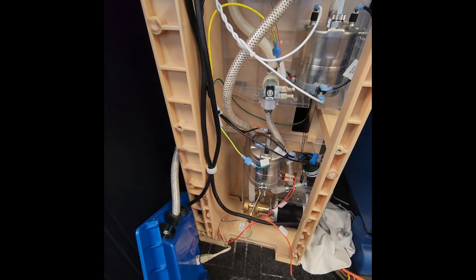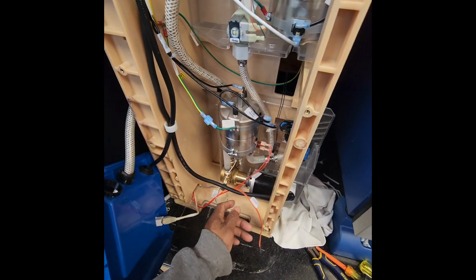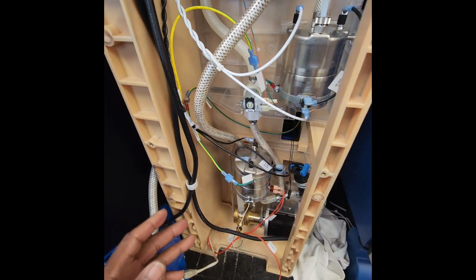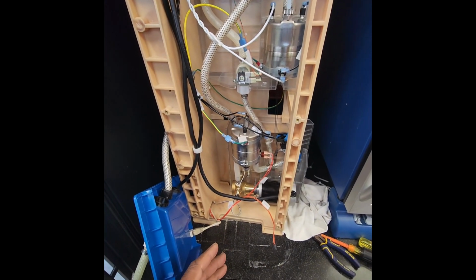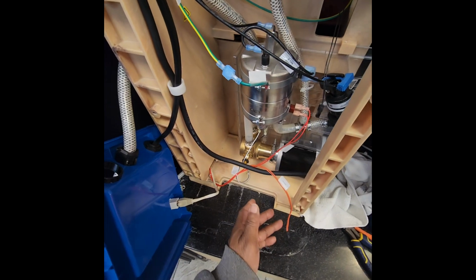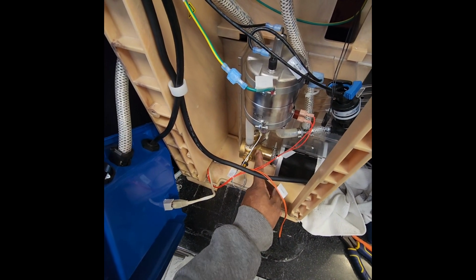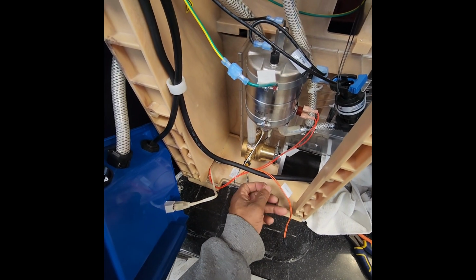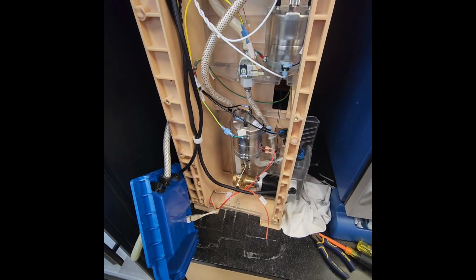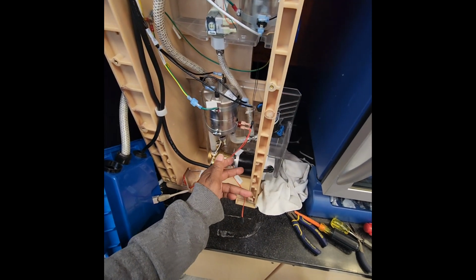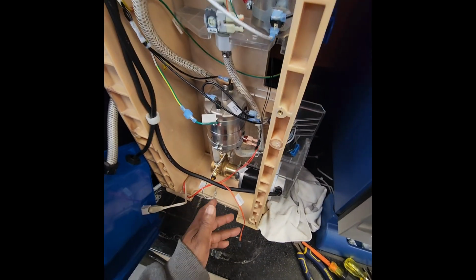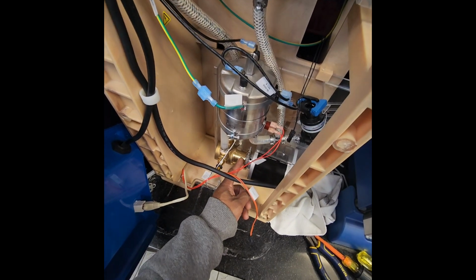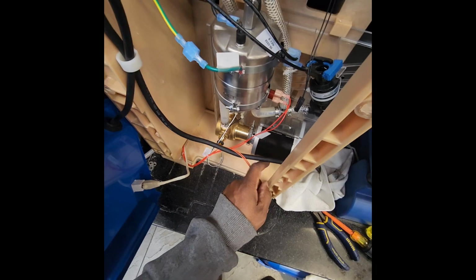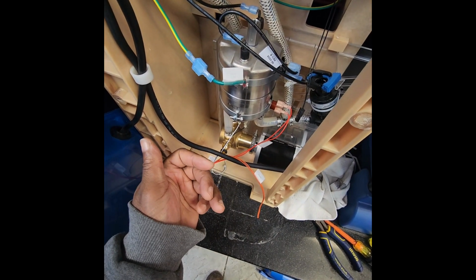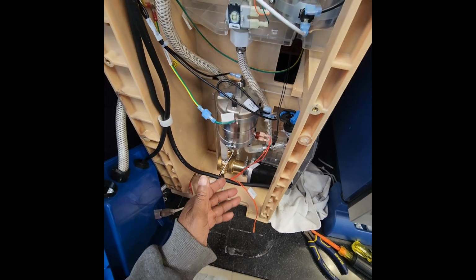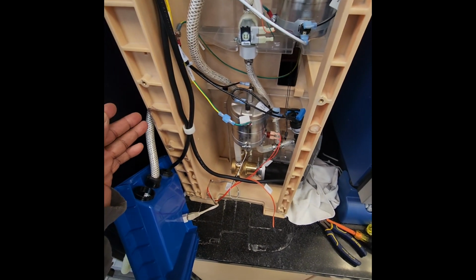I know it seems like extra work, seeing as the pump motor is indicating it has a short of some type, or it's tripping the breaker. That's what I thought when they asked me to separate the motor and the pump to see which one was bad, if any. I wondered why not just send out the whole assembly, but on their end, they don't want to replace the whole assembly if they can just replace the Procon pump or the motor, and then the board, because that's going to help determine for sure if you need to replace the board.